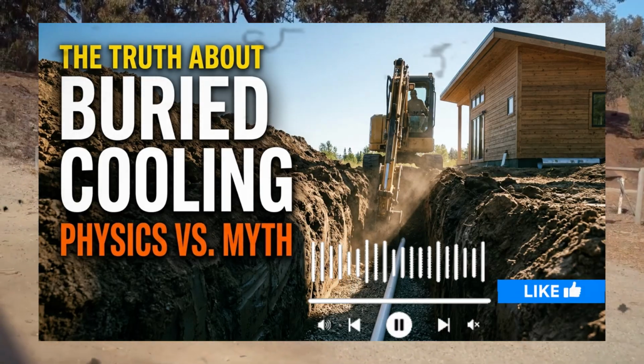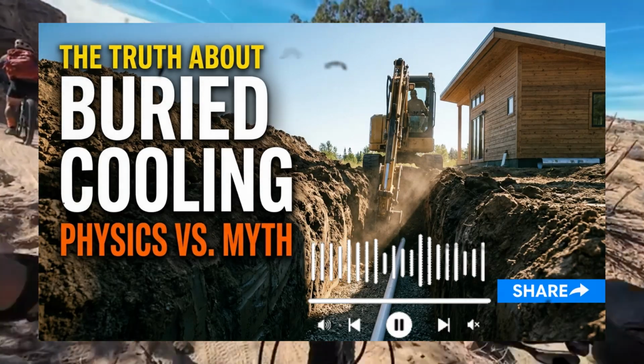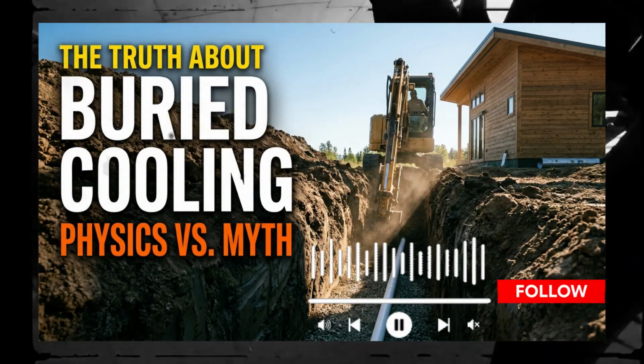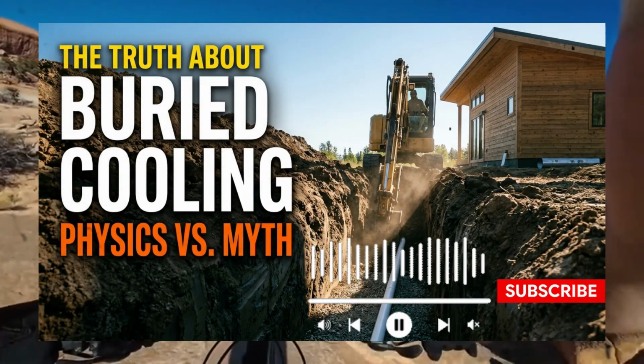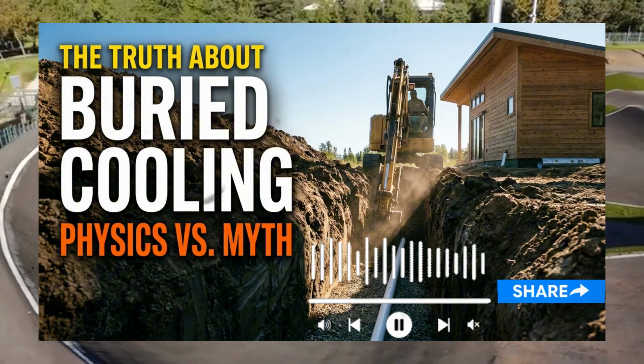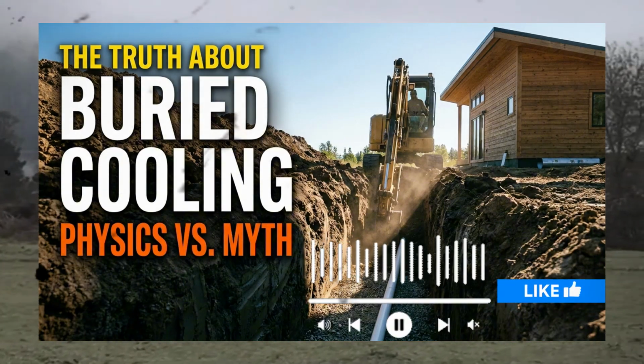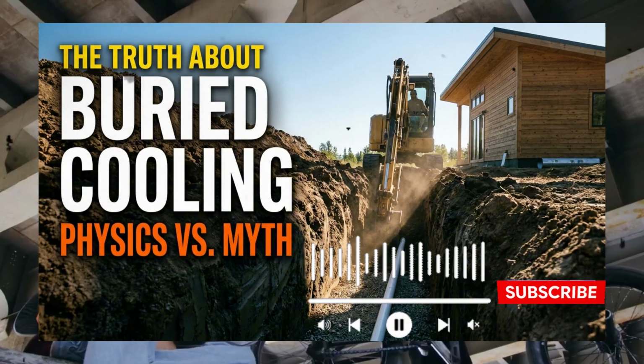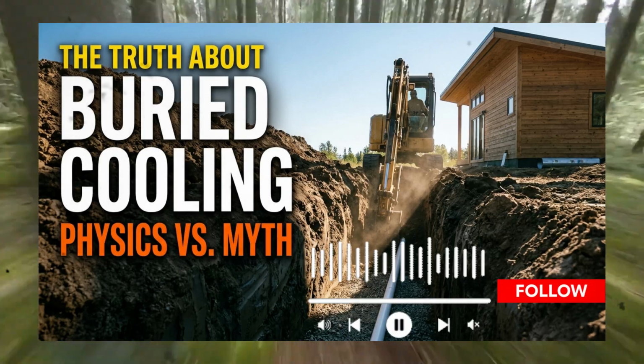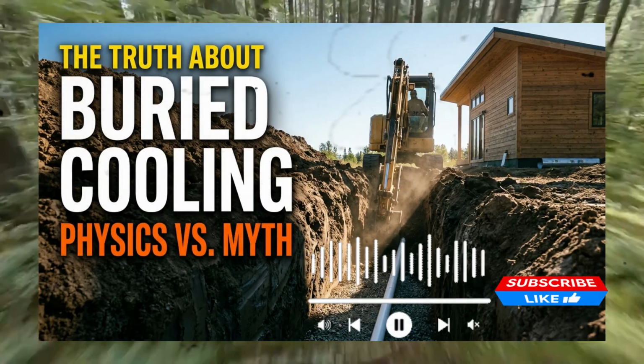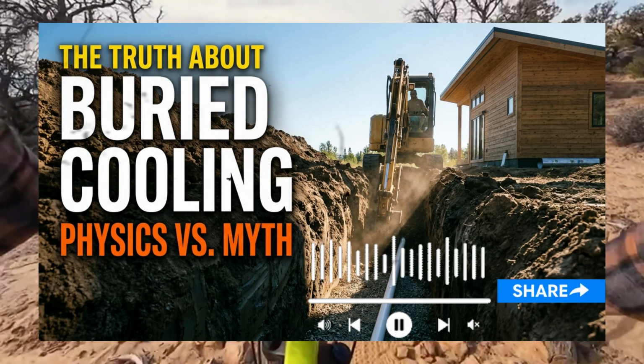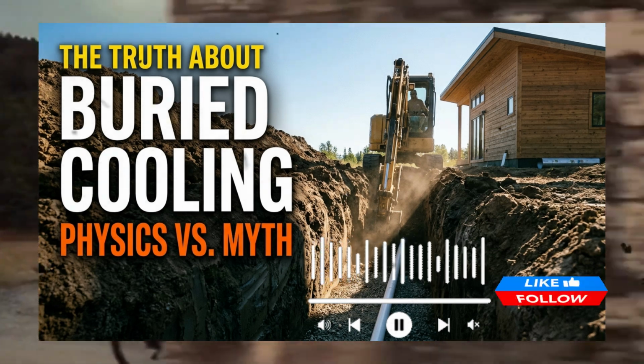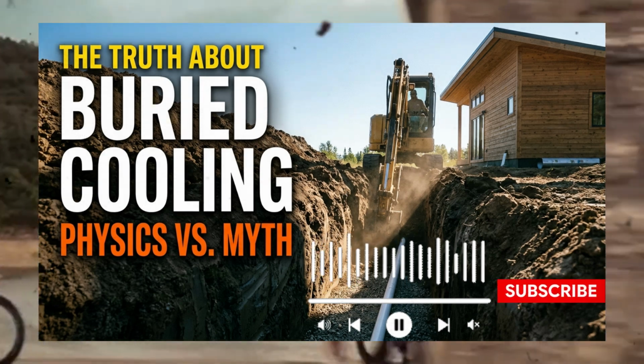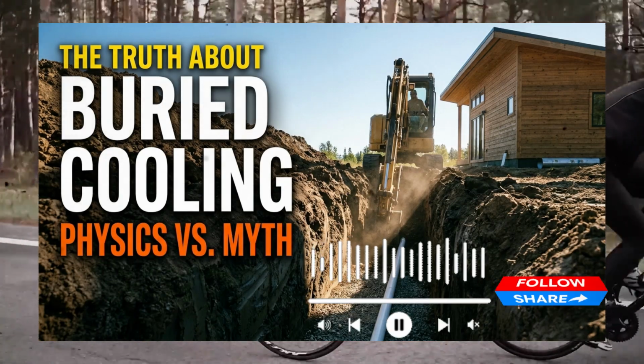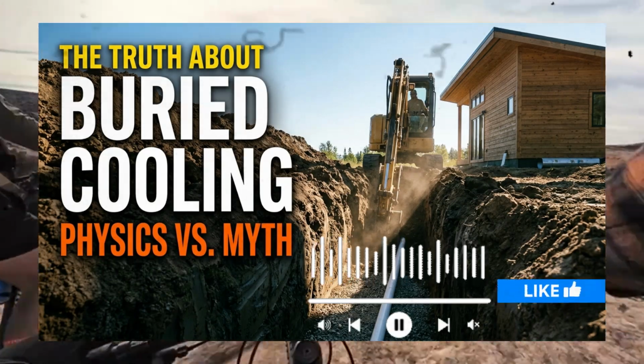If a single joint leaks, the surrounding groundwater can seep into our clean air channel, carrying sediment and surface contaminants with it. As we began dry-fitting the pipe runs in the trench, we encountered our first major aerodynamic bottleneck, and this brings us to our first critical engineering layout mistake. If you place a single 90-degree elbow in your underground run, you can restrict the airflow so severely that your inline fan will burn out within a few short weeks.